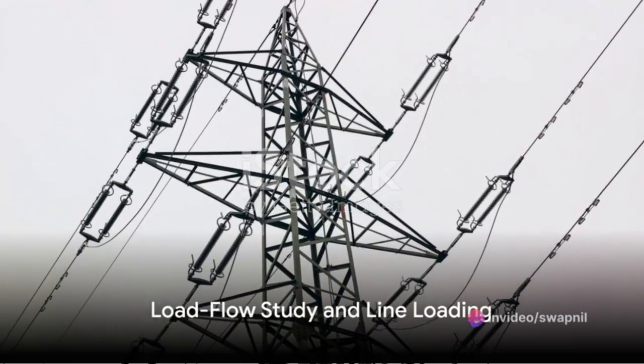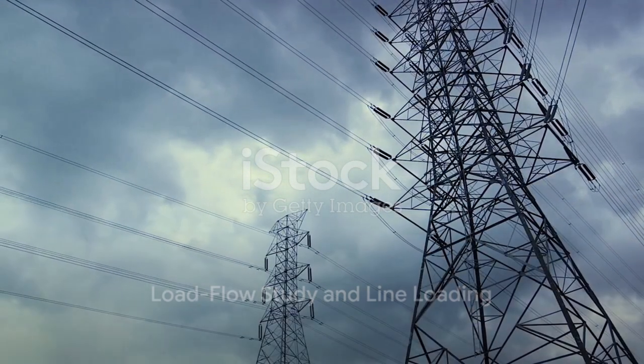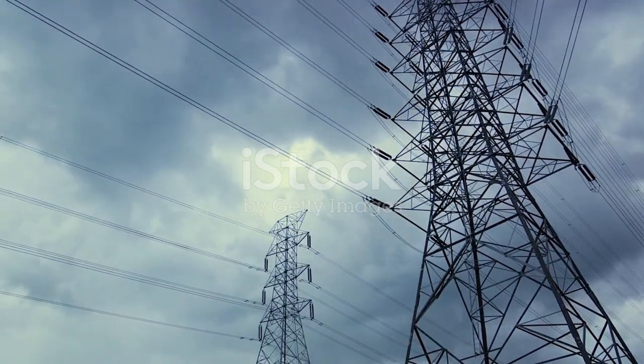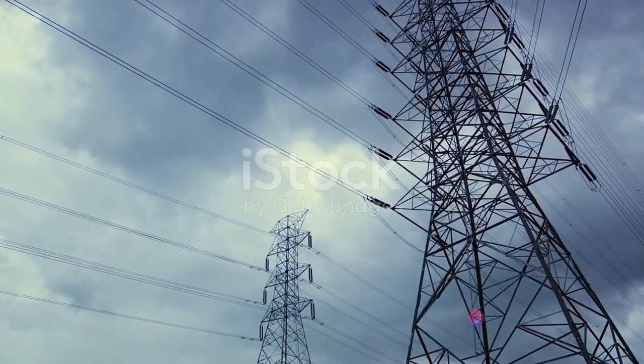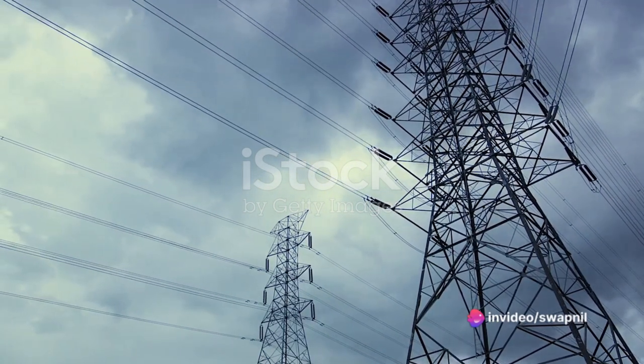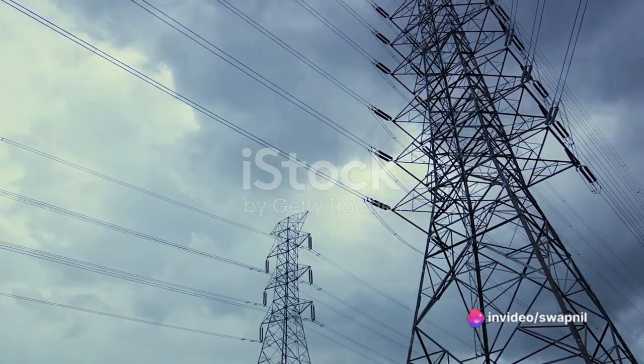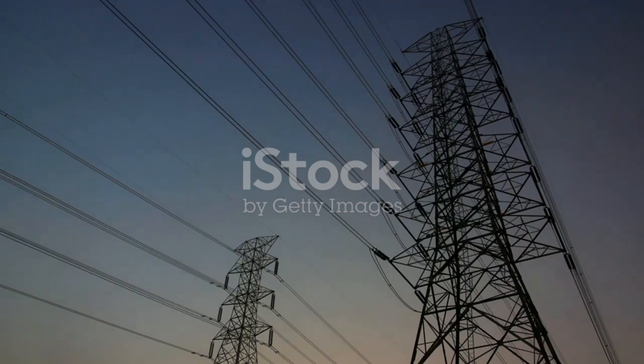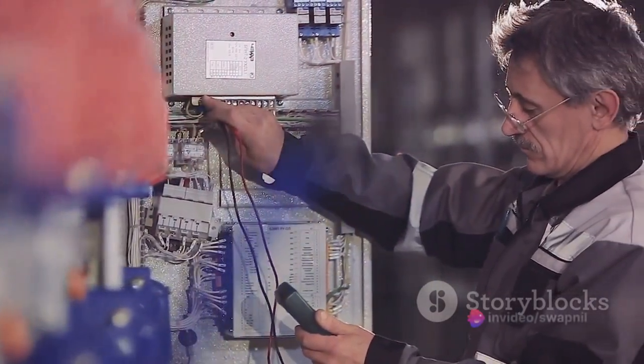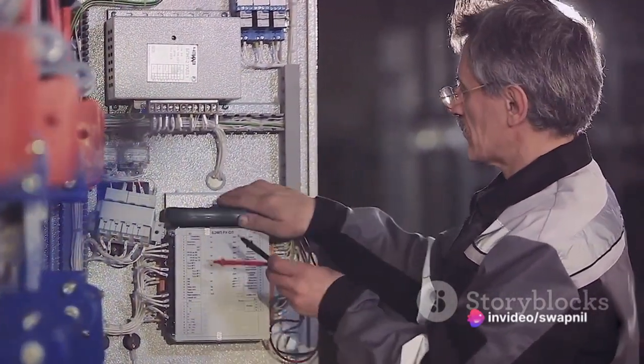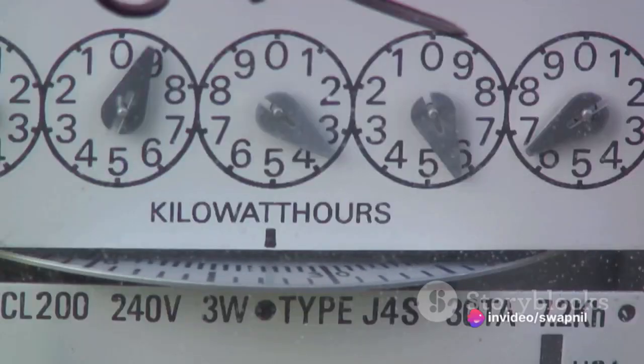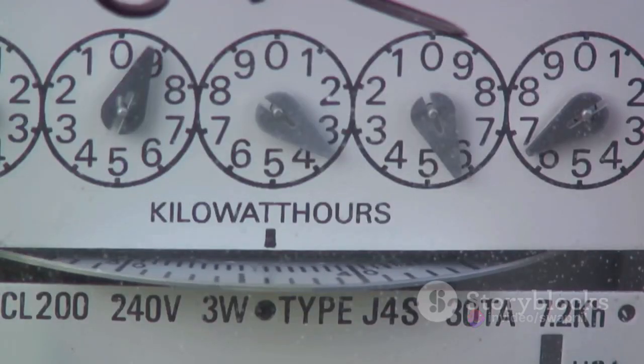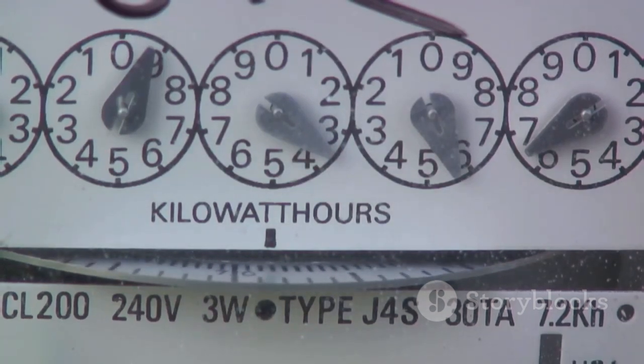In a complex interconnected AC transmission network, the source to a load power flow finds multiple transmission paths. A load flow study must be performed to determine the levels of active and reactive power flows on all lines. The flow of active and reactive powers on a line is determined by its impedance and the voltages at its terminals. Despite the reliability of interconnected AC transmission networks, there is no control over line loading. However, series and/or shunt circuit elements such as capacitors and reactors can be added to modify loading capacity.